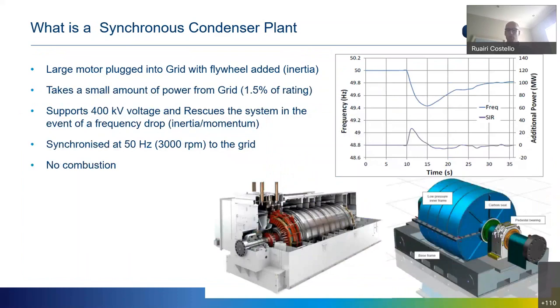Just briefly to describe what a synchronous condenser plant is. It's a large motor plugged into the grid. We've added the flywheel to increase the mass of that, which increases the inertia on the system. It takes a small amount of power from the grid, about 1.5% of rating. And its job is to support the 400 kV voltage at Money Point. It'll rescue the system in the event of a frequency drop.